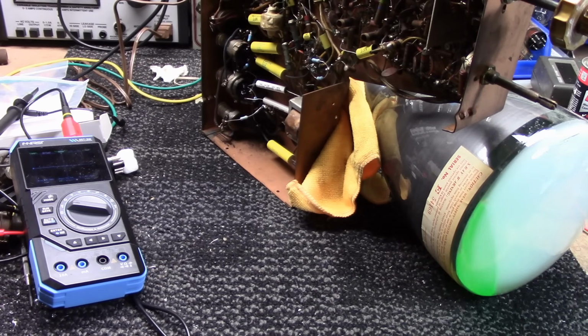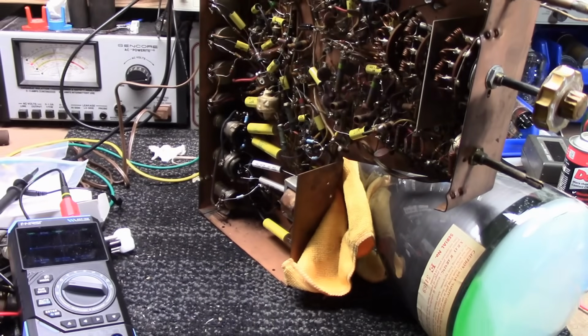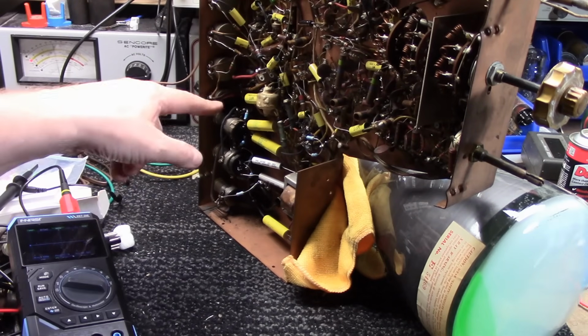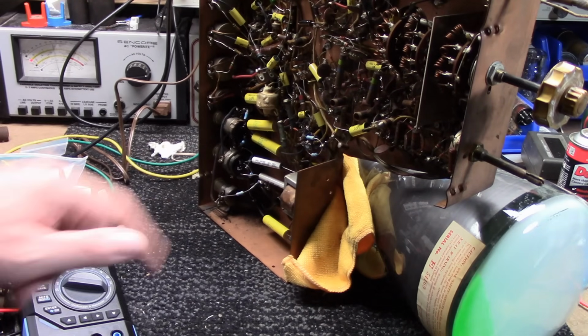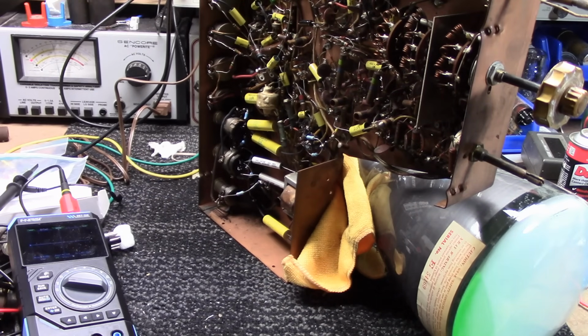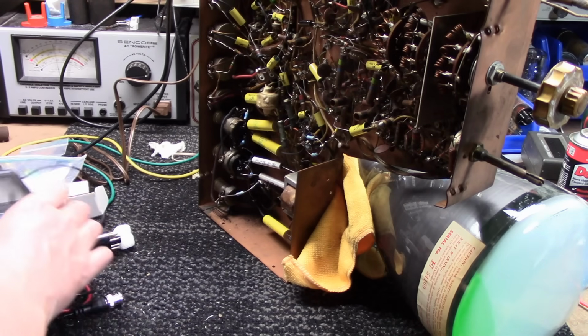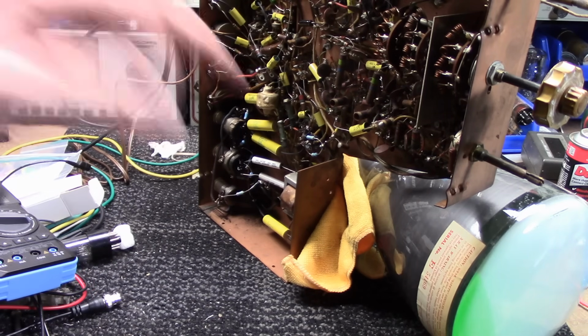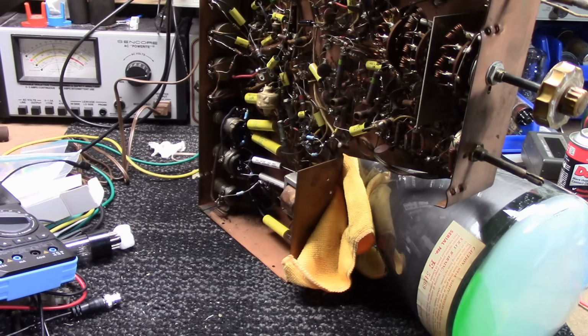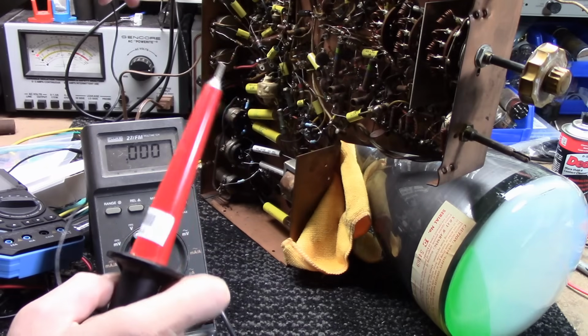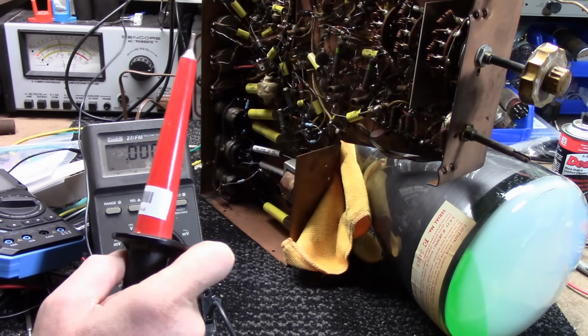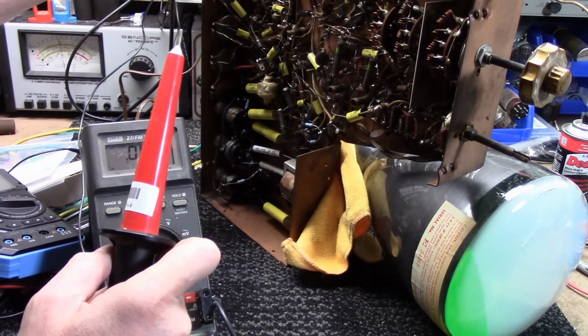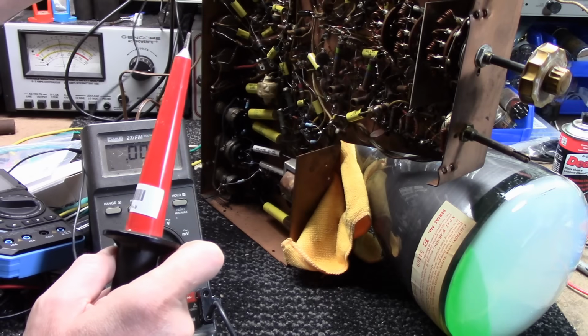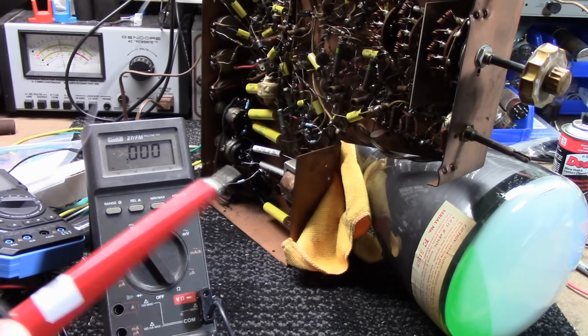Well, we can get a high voltage probe and check on each lug, go into those caps, and we should have somewhere around 4,000 to 5,000 volts on each of those lugs, because there's a DC offset combined with that AC sawtooth. Now there are other possibilities. Another really simple one is maybe the wire going to that one deflection plate just broke from flexing.